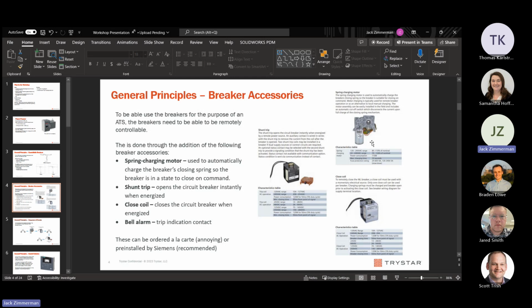The closed coil too, that's something that we add to it for this case to work with the spring charging motor. That's different than the standard trip coil that would be in it that we'd use with the actual pump panel. You add that to be able to do it remotely, basically. So the closed coil is just the opposite of this shunt trip. All it is, you have some kind of voltage, which you can decide based on what you need, whether it's 120, 480, or 24. And you just apply that voltage to the closing coil and it automatically closes the breaker up. It does work in tandem with the spring charging motor, but not directly.